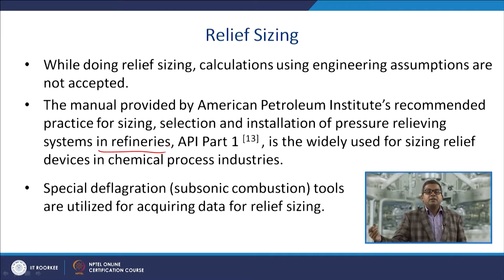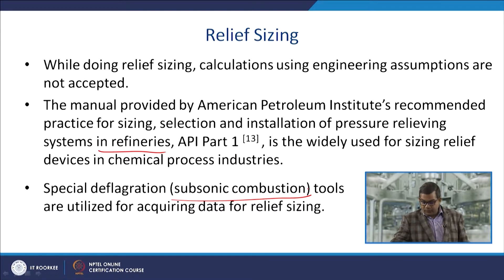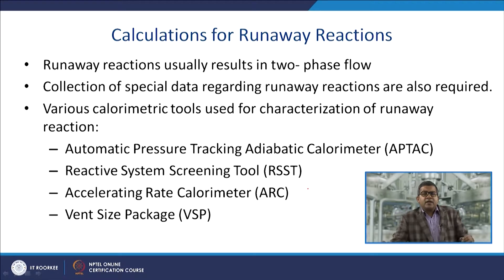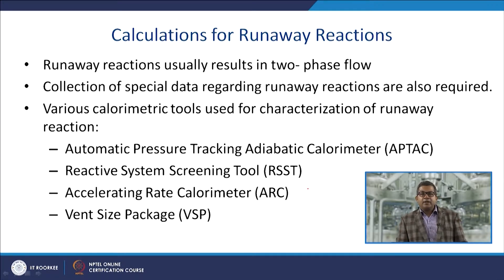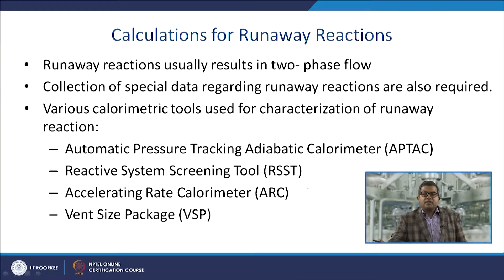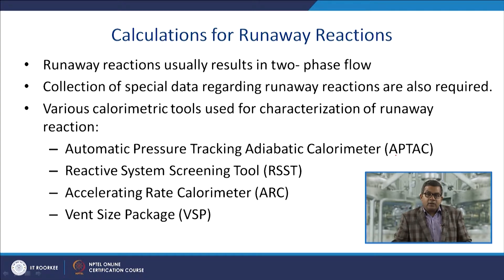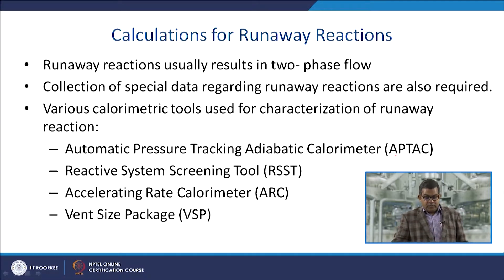Special deflagration (subsonic combustion) tools are utilized for acquiring relief sizing data. For runaway reactions, which usually result in two-phase flow, special data collection is required. Various calorimetric tools are used for characterizing runaway reactions, including Automatic Pressure Tracking Adiabatic Calorimeter (APTAC), Reactive System Screening Tool (RSST), Accelerating Rate Calorimeter (ARC), and Vent Size Package (VSP).